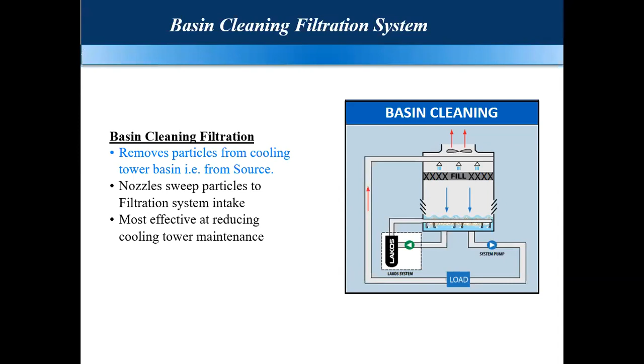And further to that, you are actually cleaning at the source. The cooling tower is the only open thing in the system. Otherwise, no entry of dust will be taking place anywhere else. So you are cleaning at the source only, where the dust is entering. That's why the basin sweeping solution is the most effective solution for filtration.